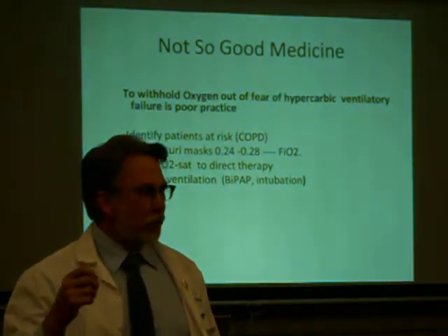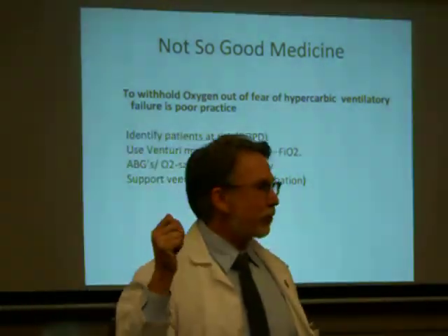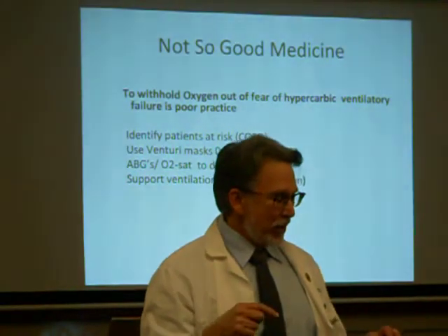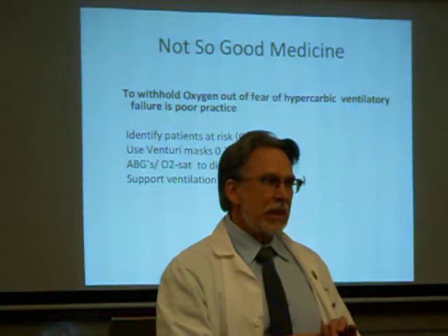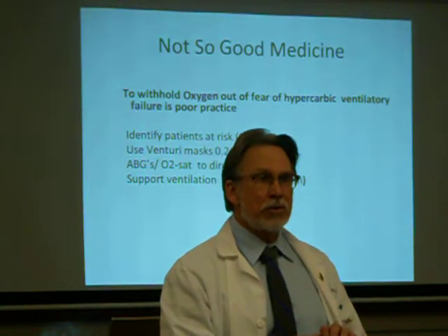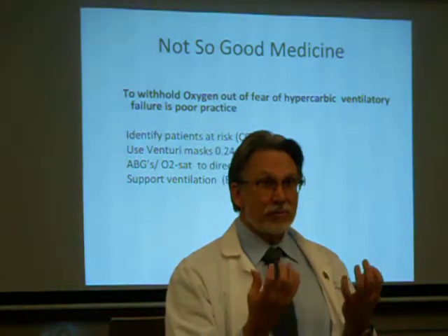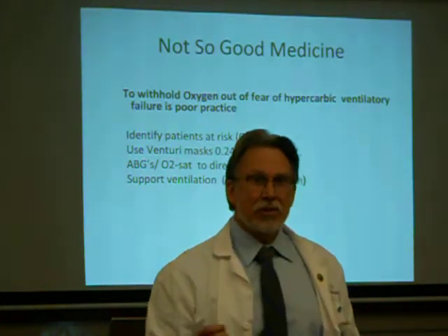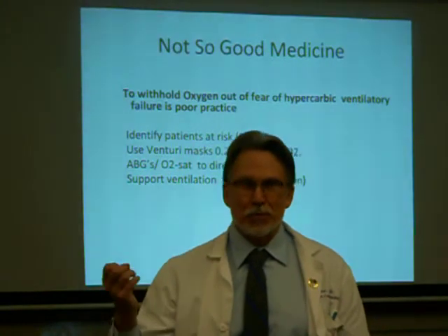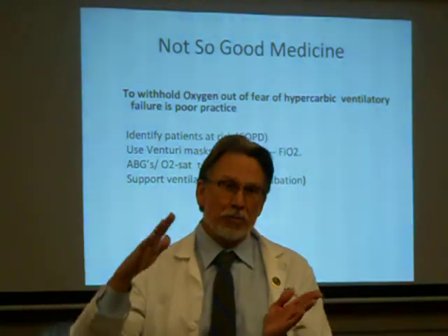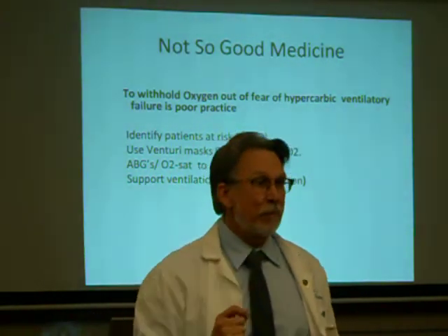And so when you set the flow meter delivering oxygen at a certain rate, the flow goes through the narrow orifice, and what happens is it entrains, it lowers the pressure around the orifice. The higher the flow rate, by the Venturi principle or Bernoulli effect, you lower the pressure around the flow.